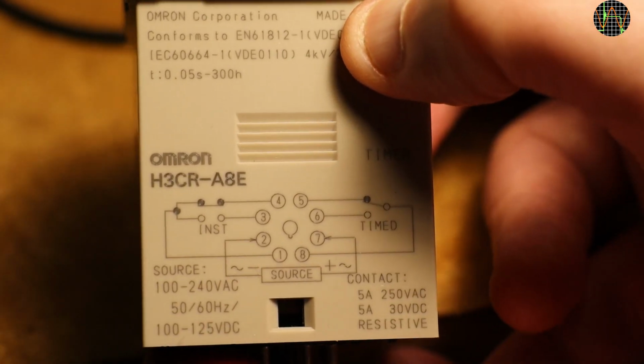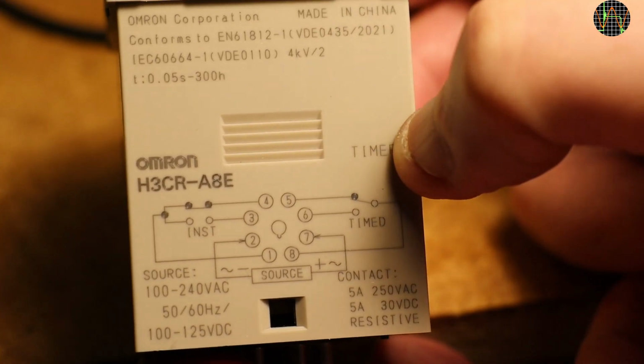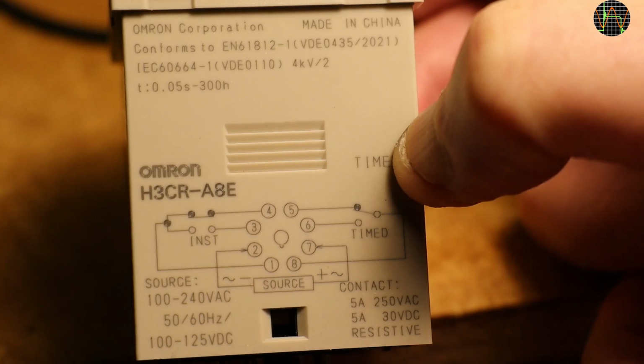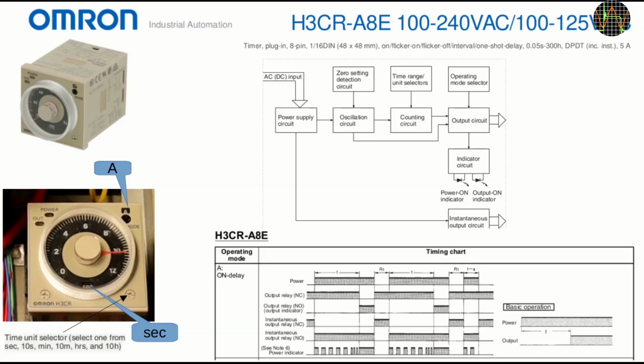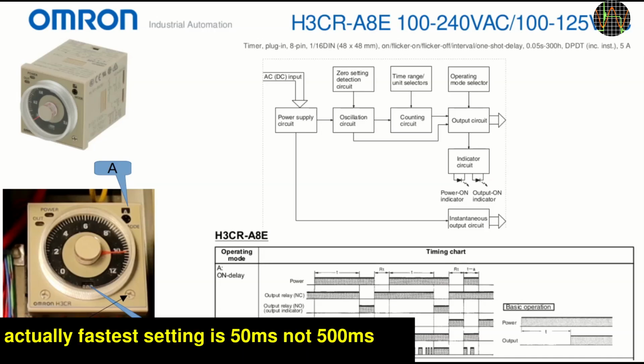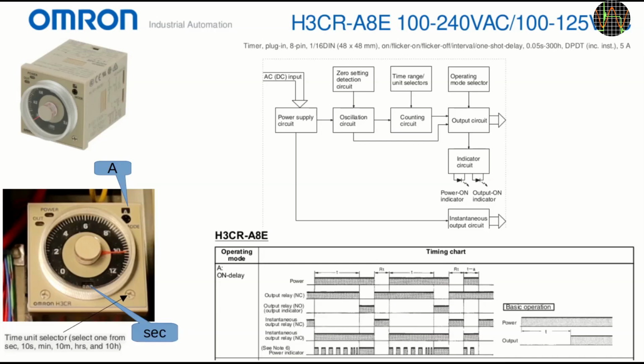Turning the unit reveals the mystery. Pins 5, 6 and 8 are for contact driven by the selected time, but pins 1, 3 and 4 are for contact that is instantaneously driven as soon as the timer is running. Datasheets for the timer are available on the web from Omron, and this thing is way more complex than what you would expect. As a start, it can do timing from 500 milliseconds to 300 hours. That alone indicates this is an electronic device, and indeed the block diagram confirms this. My unit is set to sec, meaning seconds, as the time unit, which can be changed using this screwdriver operated selector, and mode A, which is another setting that can be changed with a control below the A.